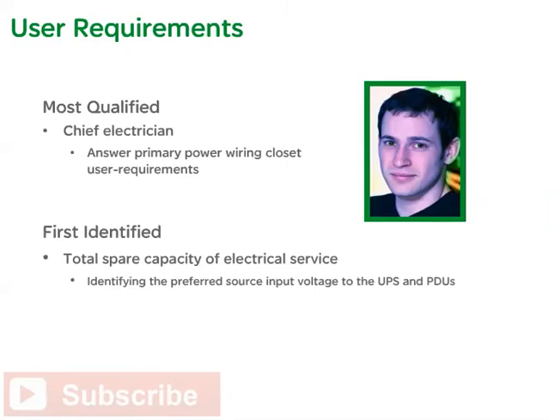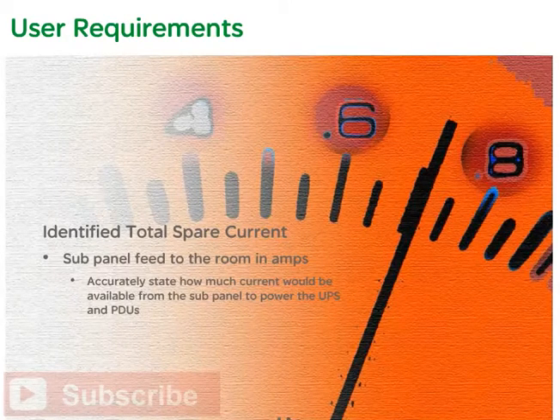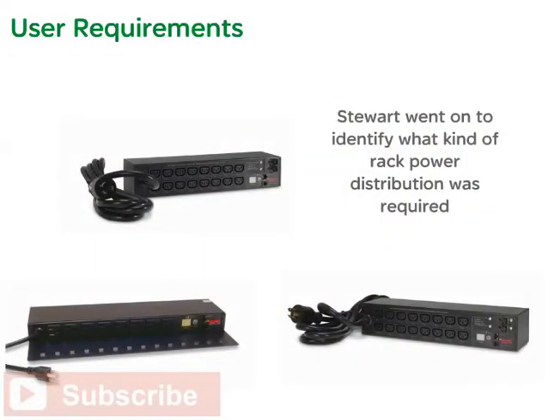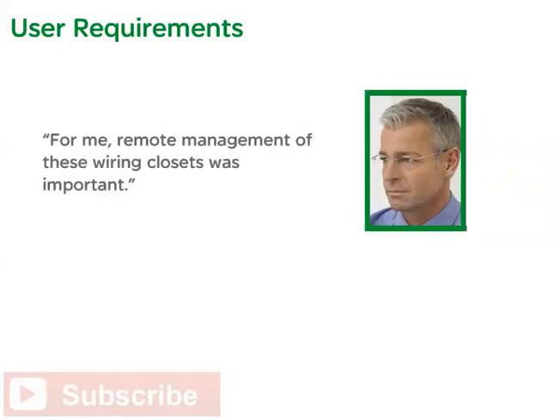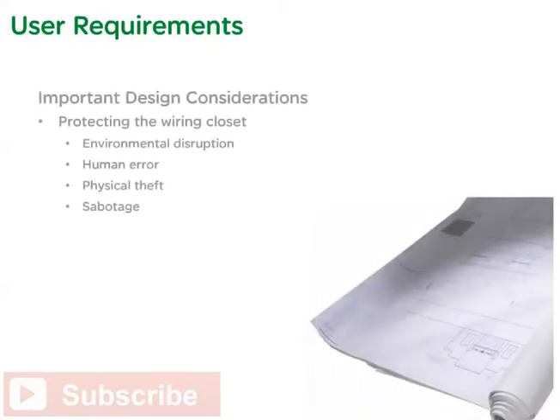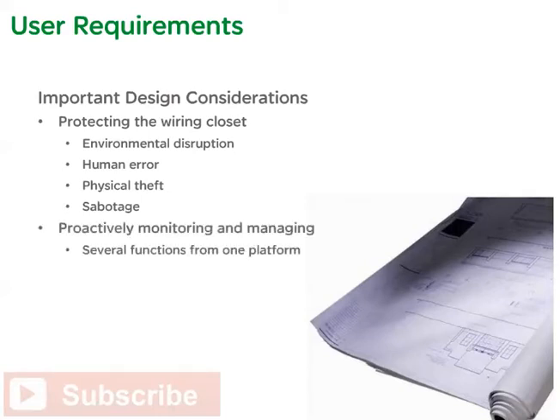Stewart first identified the total spare capacity of the electrical service entrance by identifying the preferred source input voltage to the UPS and the PDUs. Next, he identified the total spare current of the subpanel feed to the room in amps, so he could accurately state how much current would be available to power the UPS and PDUs. Finally, Stewart identified what kind of rack power distribution was required. Remote management of these wiring closets was important — he wanted to monitor how much power was going into the rack and wanted control over power going into individual rack outlets. For this reason, Stewart recommended that power be distributed via a switched rack power distribution scheme.